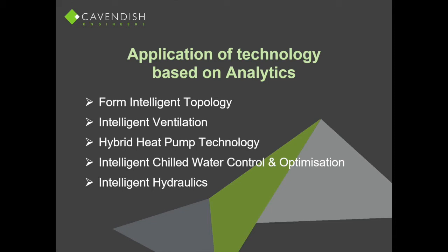By using hybrid heat pump technology, if you specify that N4 platform to be in the product when it's delivered, then as you take one out and plug it in again, you're plugging it straight into the N4 platform and not the BMS. The reason you need to do that is that the BMS becomes a slave - the machine interacts with the cloud, with the N4 platform, and it tells the BMS what to do. So you don't have to strip it out, you just reuse the older BMS.